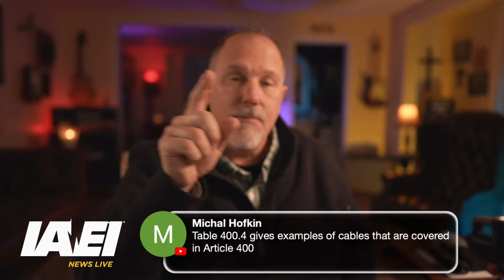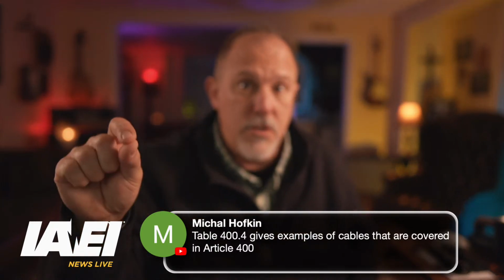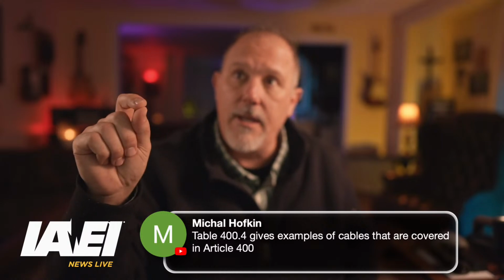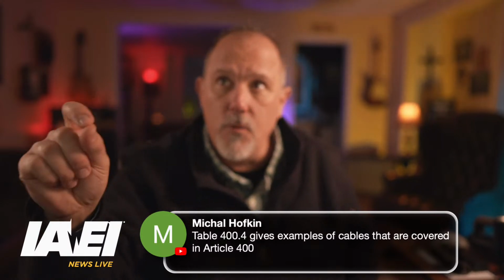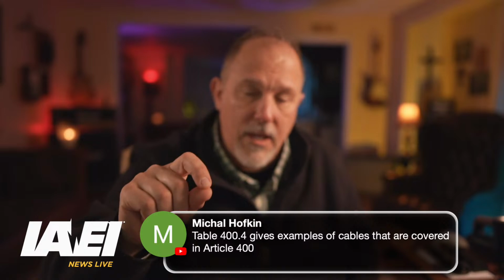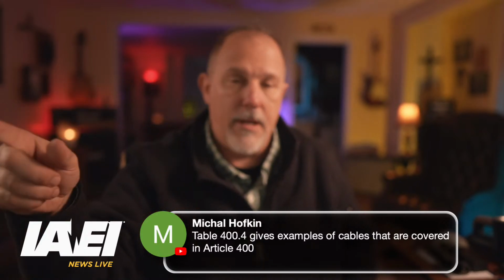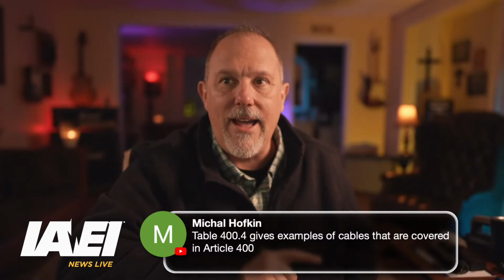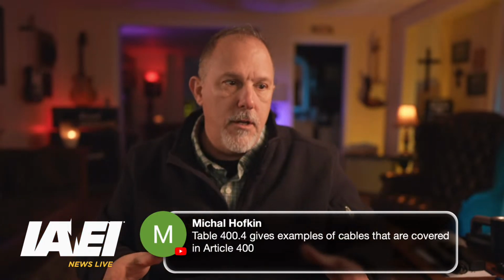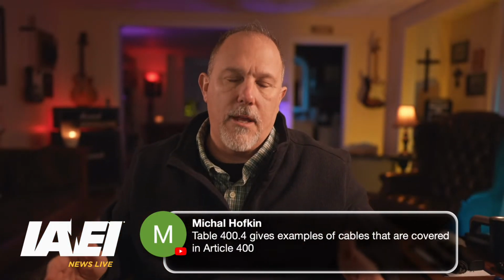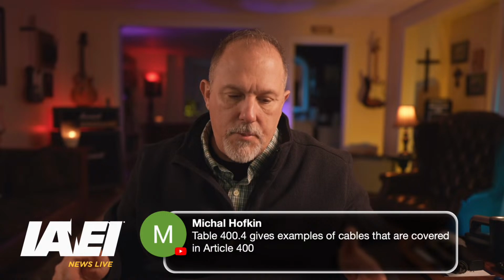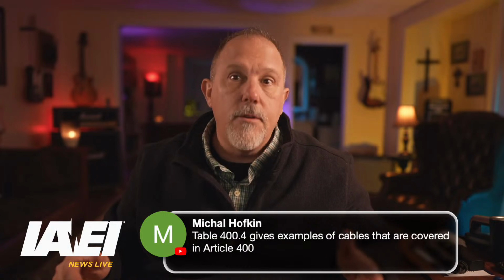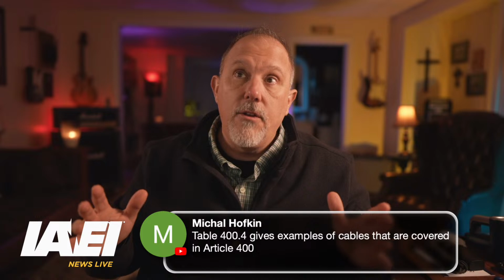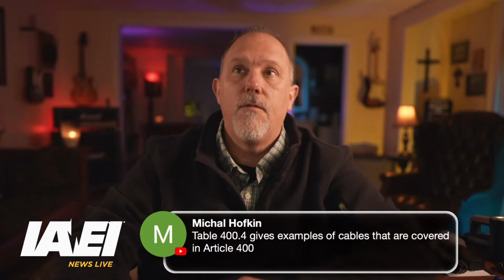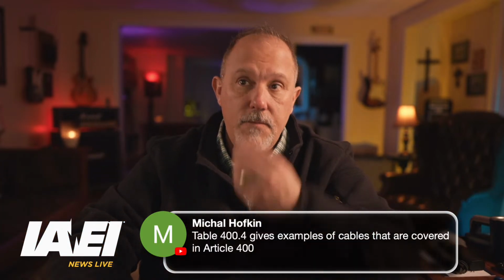Then, to help you do that, you would look at your dot 3 in fixture wires and your dot 4 in flexible cords and flexible cables, and look at the type letters, compare that to what you have, and now you're in the ballpark. You may not be in the pew, but you're in the right row, and you have a whole line of pews for the requirements for that application.